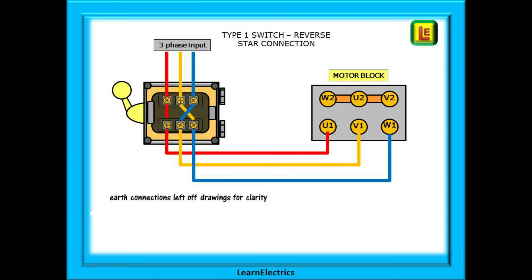Put the motor in reverse and the crossover comes into play. L1 input goes to U1 as before, but L2 is now crossed over and goes to W1, whilst L3 goes to V1 on the motor block.